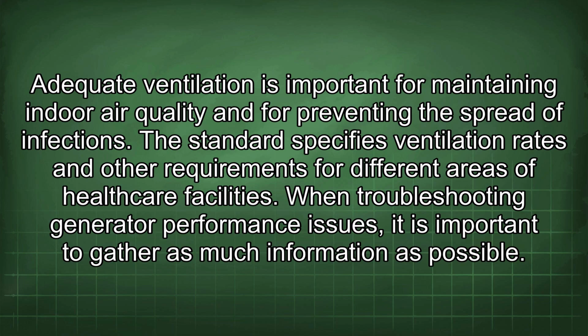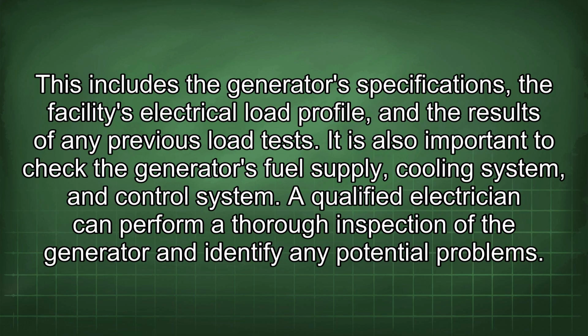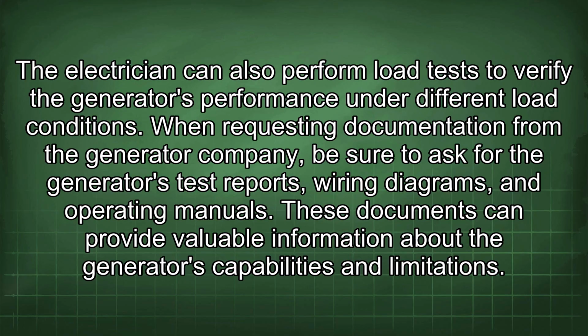When troubleshooting generator performance issues, it is important to gather as much information as possible. This includes the generator's specifications, the facility's electrical load profile, and the results of any previous load tests. It is also important to check the generator's fuel supply, cooling system, and control system. A qualified electrician can perform a thorough inspection of the generator and identify any potential problems. The electrician can also perform load tests to verify the generator's performance under different load conditions.